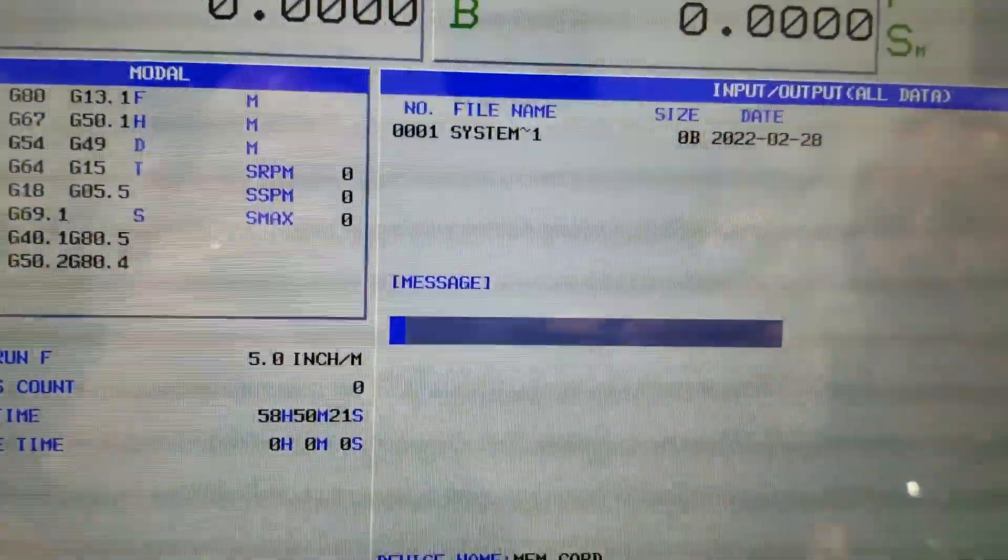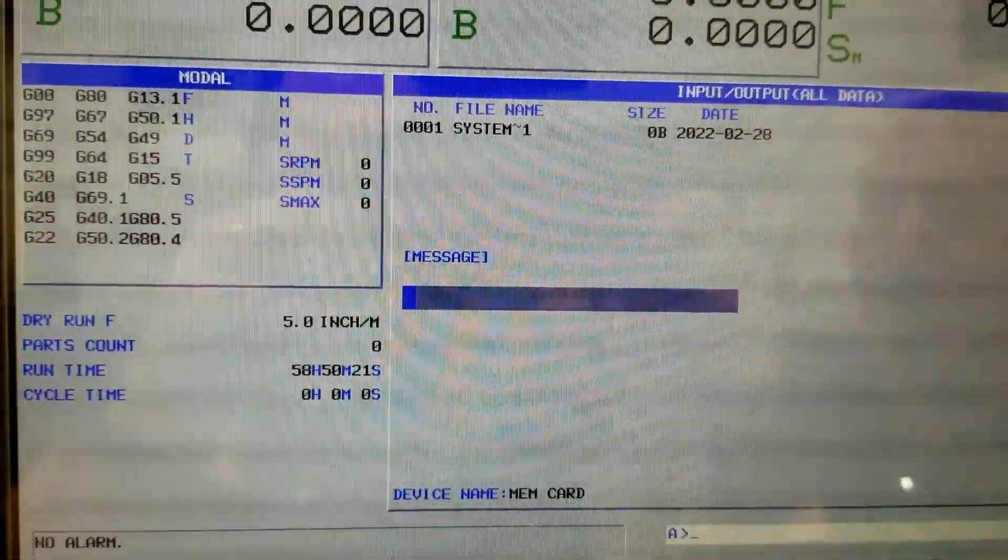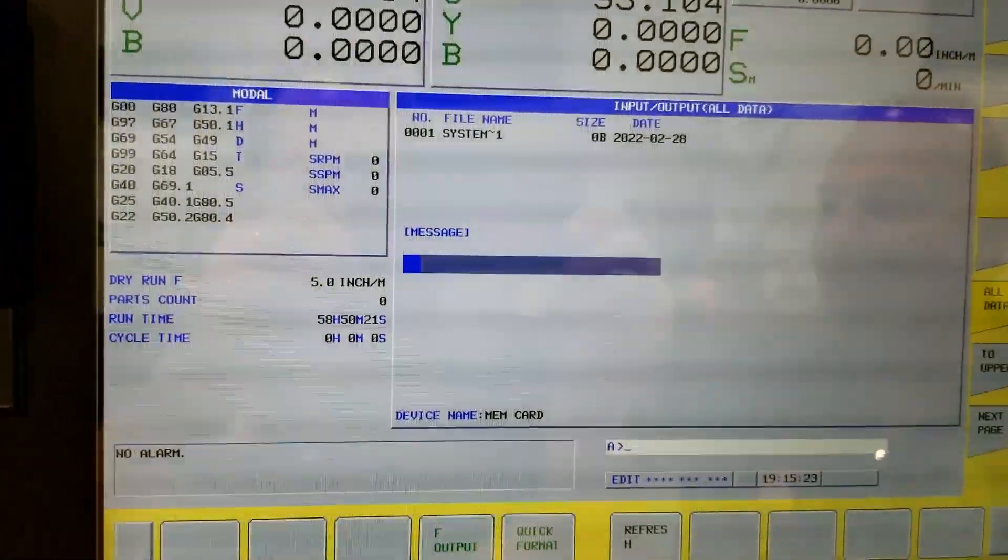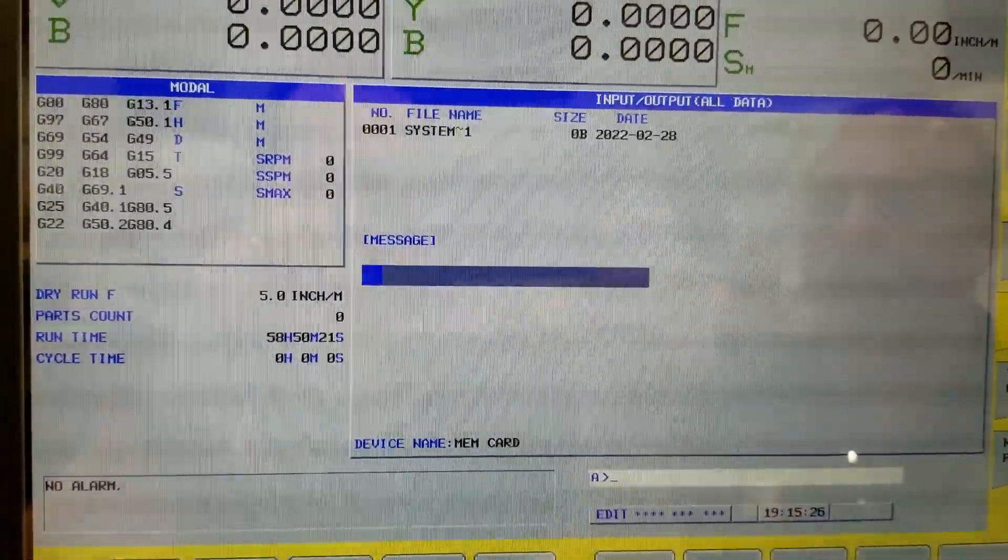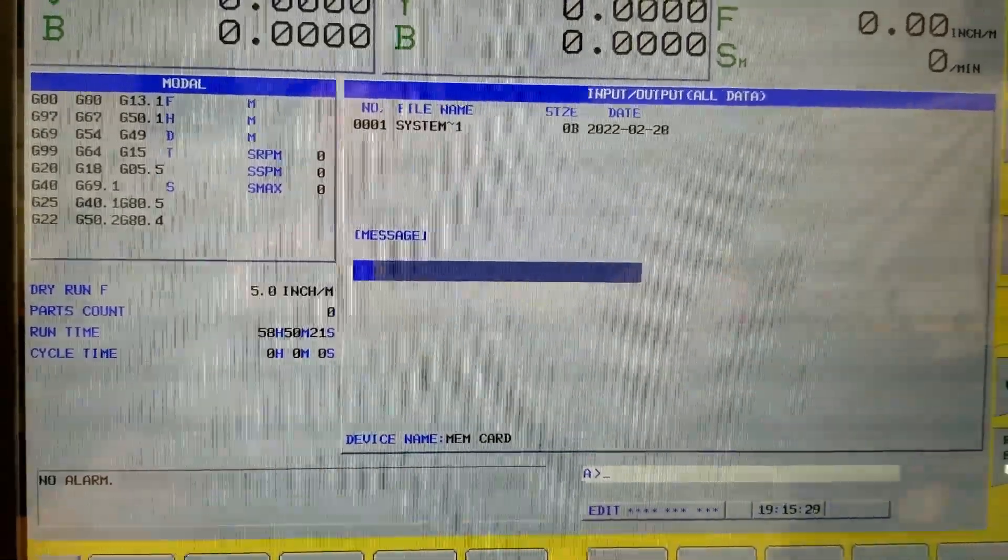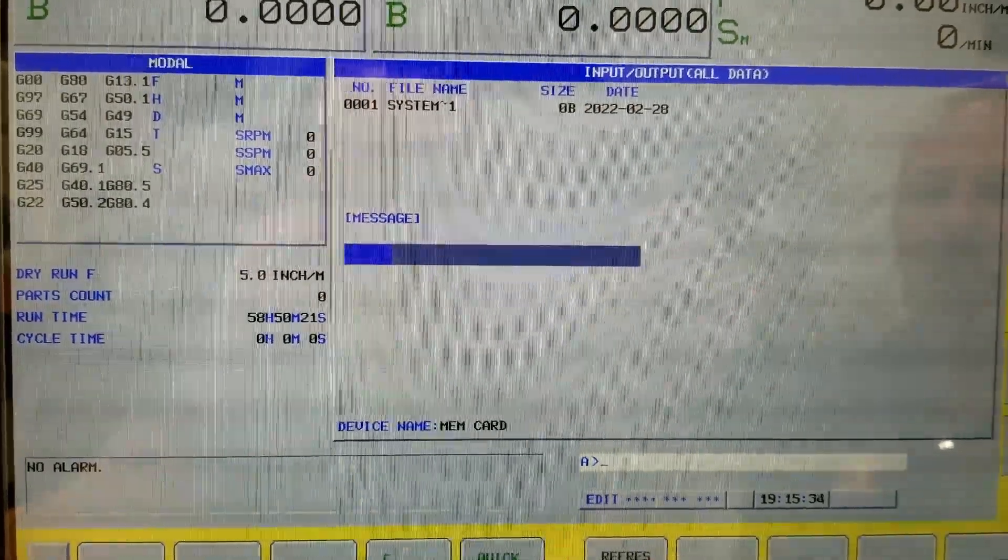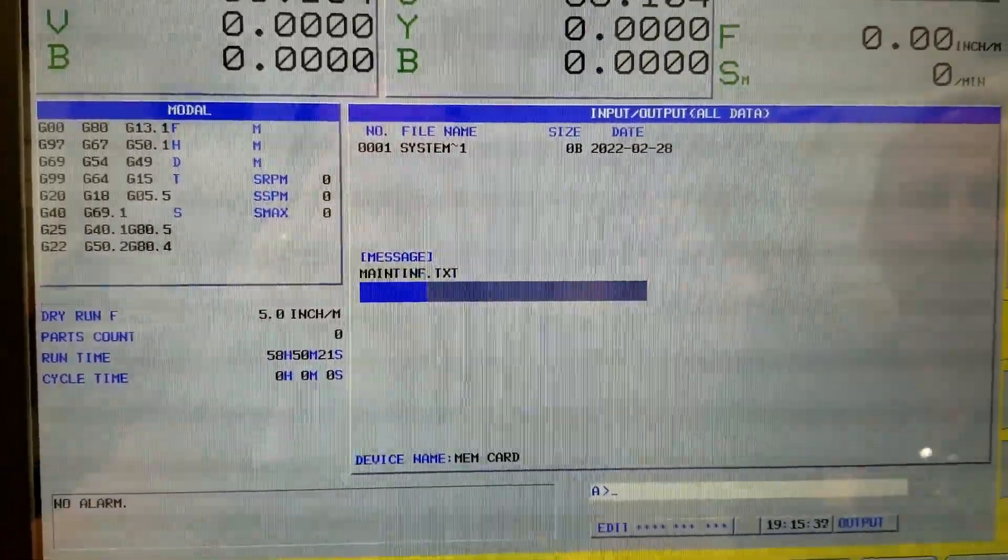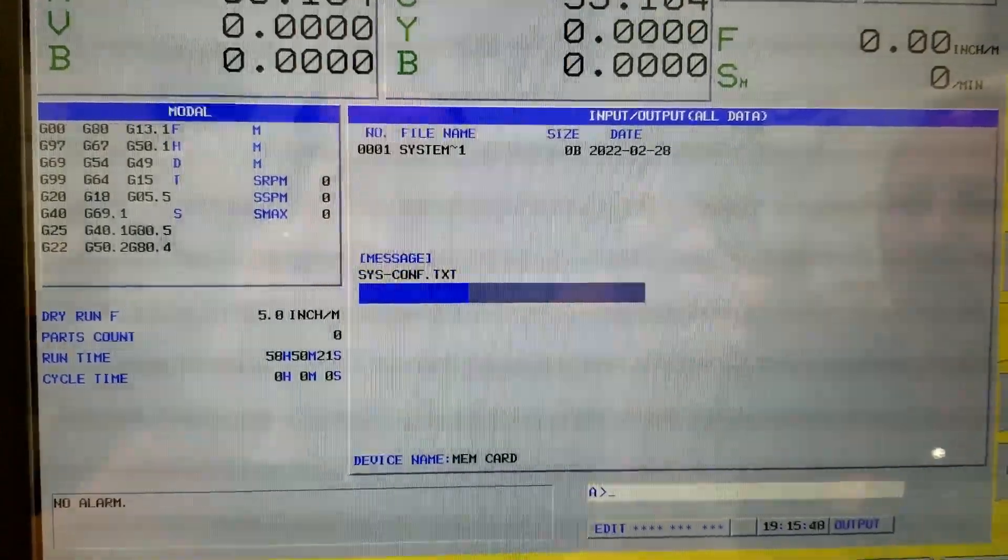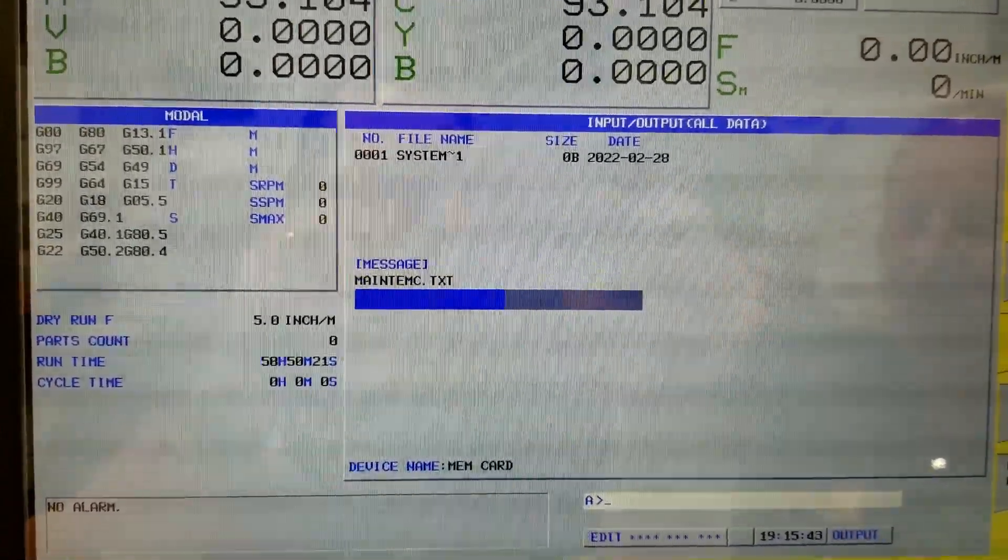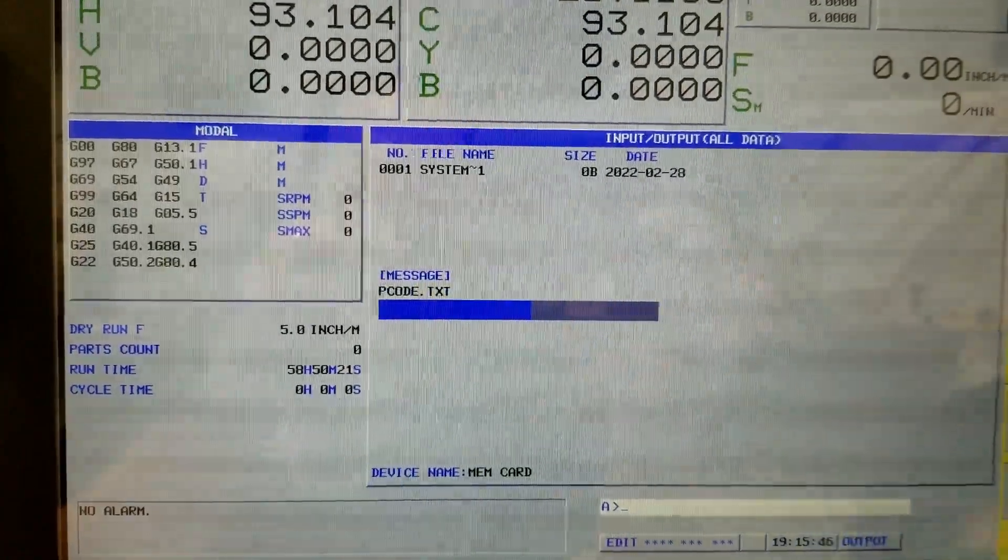Now this backs up everything. It takes the parameters, the timers, counters, keep relays, offsets, programs—it takes everything out. This usually takes a minute or two to complete, and once it's done it's going to prompt us to cycle the power on the controller. We don't need to turn off the main disconnect, just the power on the control itself.